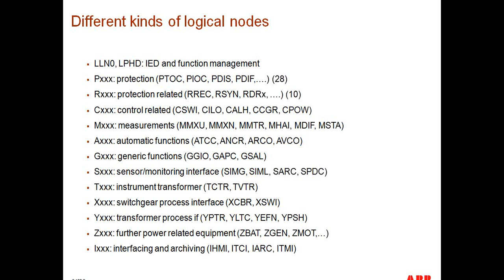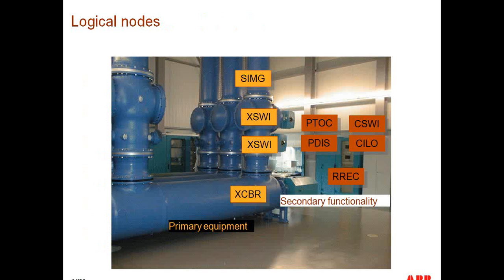So as you can see, when the standard was being written, they were thinking about the domain of a substation: what are the functions that are performed in a substation, and what's the equipment that's part of the substation. And there is a logical node for the most part for each one of these. There are logical nodes for HMIs, logical nodes for current, and logical nodes for transformers, for example. And this was the idea. I have a substation, okay? There are functions and equipment, okay? In this particular case, we have a monitoring logical node. We have logical node representation of switches. We have logical node representation of a breaker via XCBR.